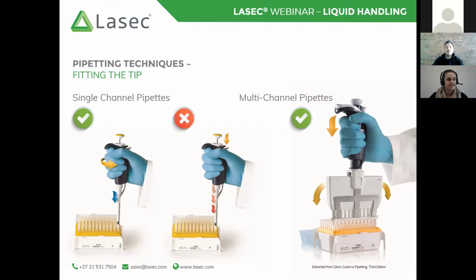All right. What we do find, and I'm sure if there are any university lecturers or supervisors doing undergrad labs, I often see it in industry as well, is that people tend to bang and hammer their pipettes into the tip rack. Obviously, this is not recommended because you do risk throwing the pipette out of calibration, but more frequently, we end up seeing cracks or fractures to the tip holders themselves. Obviously, by damaging that tip holder, you damage the vacuum inside that pipette, and without a vacuum or a partial vacuum, you are not going to be able to aspirate. So you are essentially damaging that pipette.